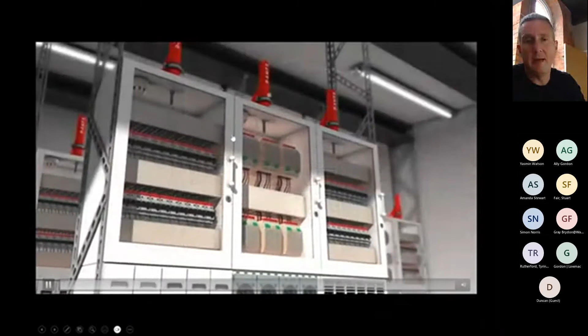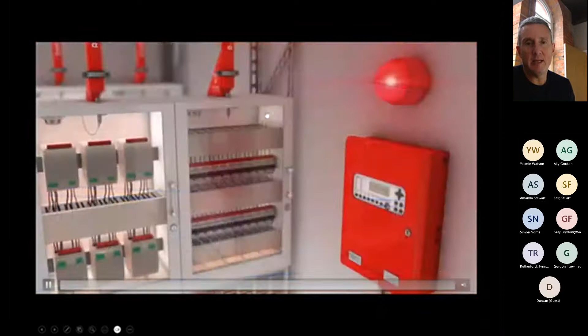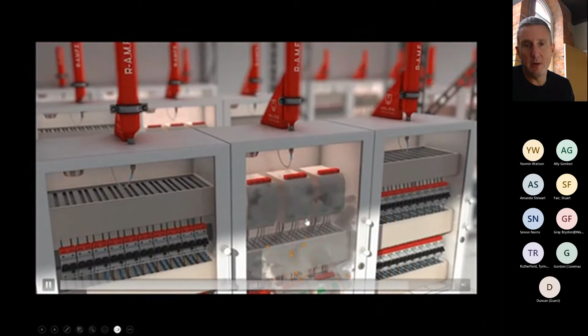We have another system called E-Detect, which is an early warning capsule, which can give us a warning of an overheating component. If that component goes into thermal runaway, we then have the AMFE cylinder automatically detecting smoke inside the cabinet. So should the AMFE system detect smoke inside, as you're going to see now, with smoke coming from the component, the detector detects it, and then the AMFE system deluges that area.